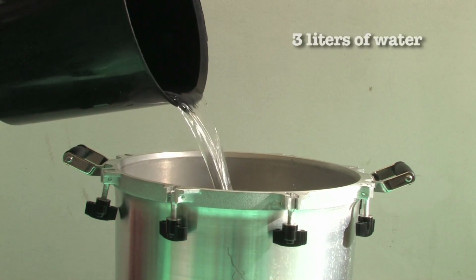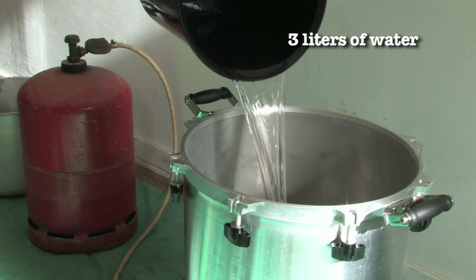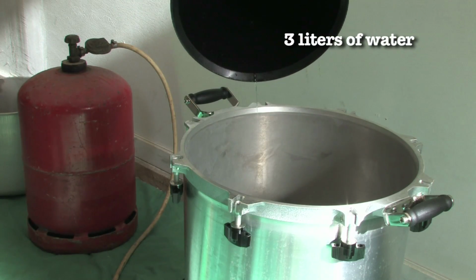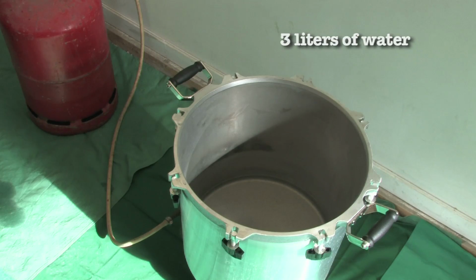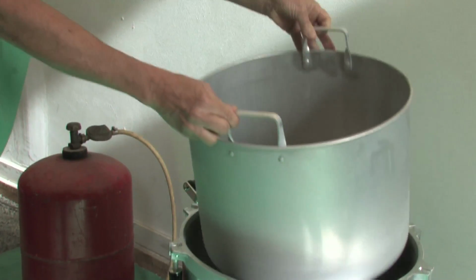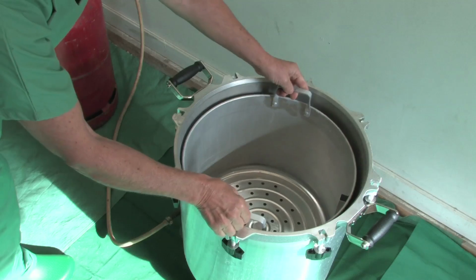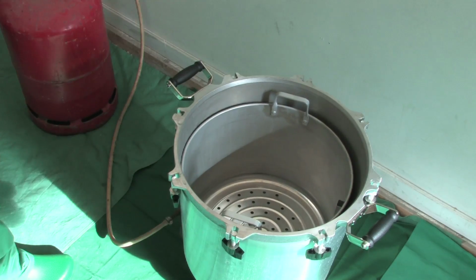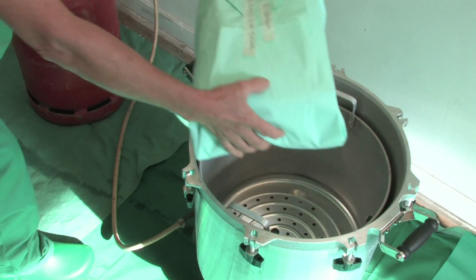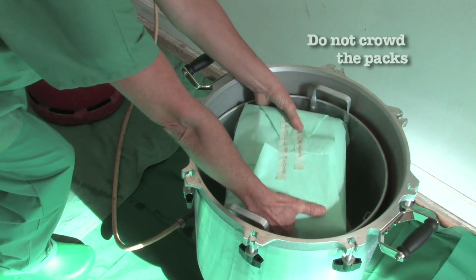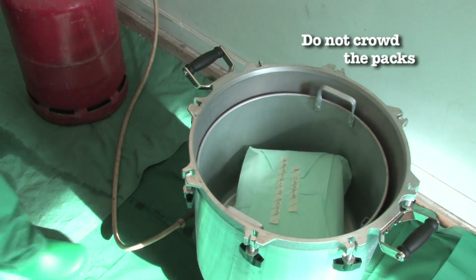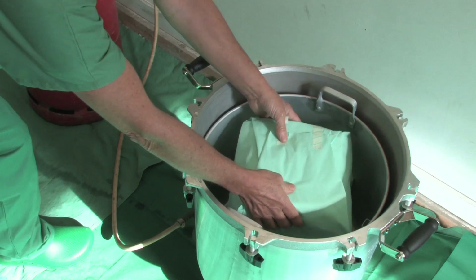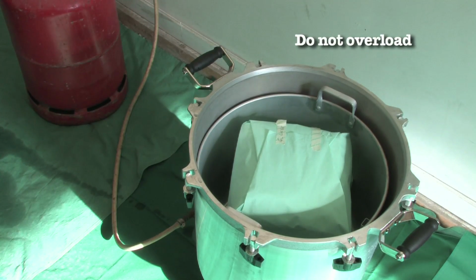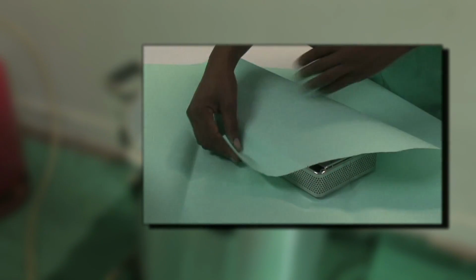1. Pour 3 litres of water in the bottom of the autoclave. Use good quality water such as bottled drinking water or filtered water. 2. Put the metal basket back into the autoclave chamber. Place the items to be sterilized in the metal basket. Do not crowd the packs so that the steam can circulate freely. Do not overload the autoclave. Load it to 2/3 of its maximum capacity. Instrument baskets should be placed horizontally.